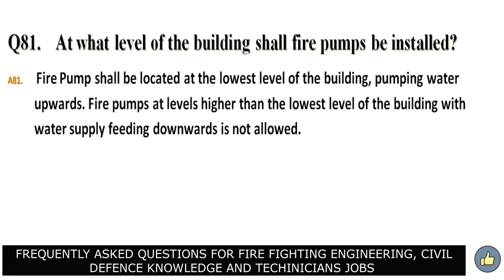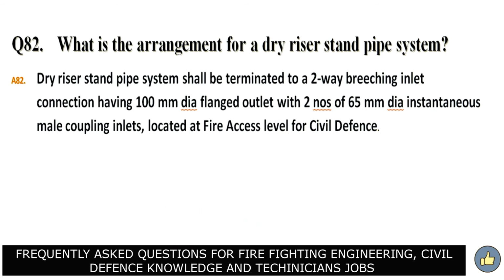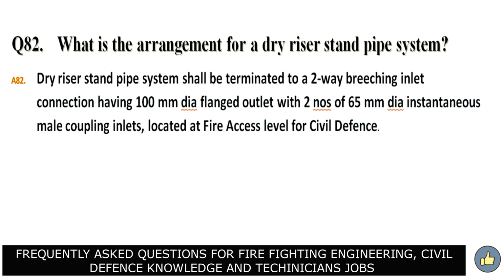At what level of the building shall fire pumps be installed? Answer. Fire pump shall be located at the lowest level of the building, pumping water upwards. Fire pumps at levels higher than the lowest level of the building with water supply feeding downwards is not allowed. What is the arrangement for a dry riser standpipe system? Answer. Dry riser standpipe system shall be terminated to a two-way breeching inlet connection having 100 mm dia flange outlet with two numbers of 65 mm dia instantaneous male coupling inlets located at fire access level for civil defense.